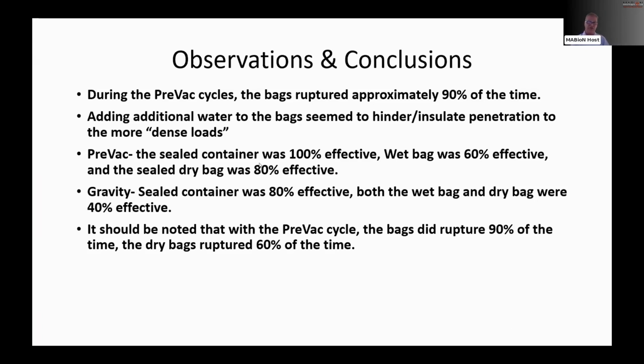The pre-vac, the sealed container, which is my product, was 100% effective on the pre-vac. The wet bag was 60% effective. You're only successful 6 out of 10 on a wet bag on a pre-vac cycle. And then the sealed dry bag with no water in it was actually 80% effective on my runs. So you're actually more effective by not adding water to it on the pre-vac.